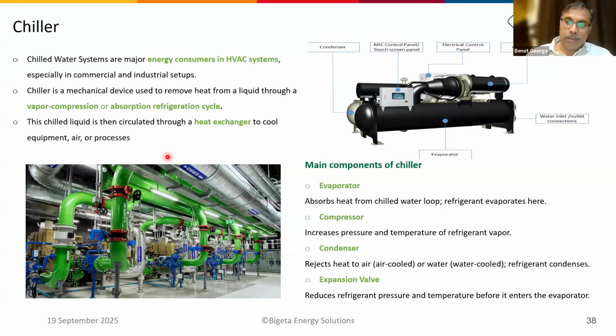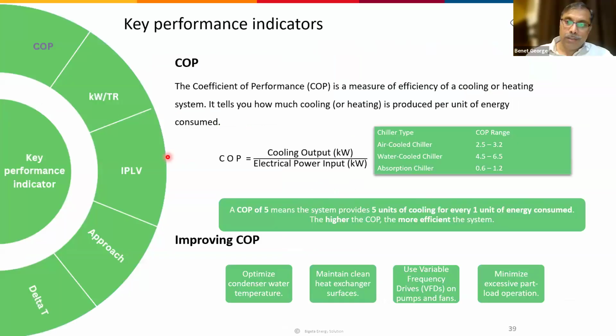Some of the key performance indicators for chillers: COP. COP is nothing but cooling output divided by the electrical power input. So the higher the COP, the more efficient it is. COP will be given in the data sheet, so you can check the COP of the chiller when you are purchasing a chiller.